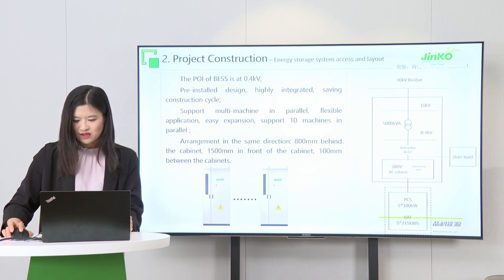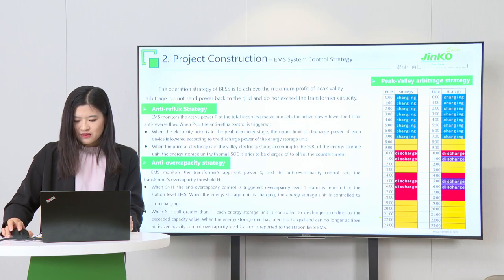Besides DC battery cabinets, a bidirectional meter is installed in the AC cabinets to measure bidirectional AC power flow between the battery energy storage system and the user load, or 0.4 kilovolt bus. Meanwhile, an anti-reflux meter is connected between the battery energy storage system and the 0.4 kilovolt bus to provide the direction of power flow to the EMS to prevent power flow going back to the grid. The EMS control strategy is explained as follows.